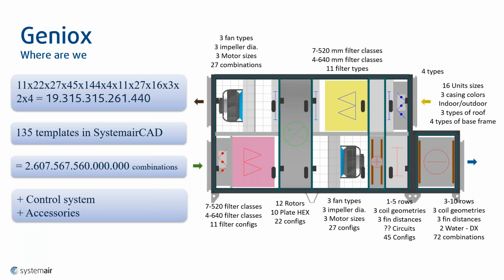Also, from a North American perspective, you will have the actual voltages available to you as well, which is another 3 options or combinations that we can multiply that by. You'll be able to get this unit in 208 3-phase, 460 3-phase, and if you do have any projects in Canada, you can get it for 575 3-phase as well. Now, this is a huge advantage because what we're finding is that some of our competitors, we're a Swedish-based company, we look at some of our other competitors which are based in Sweden, they sell units to you which are generally 400 volt, and then once the unit arrives on site, you have to scramble to try and find a transformer so that you can go from a 400 volt unit. So we'll actually have that. There's no surprises on site.